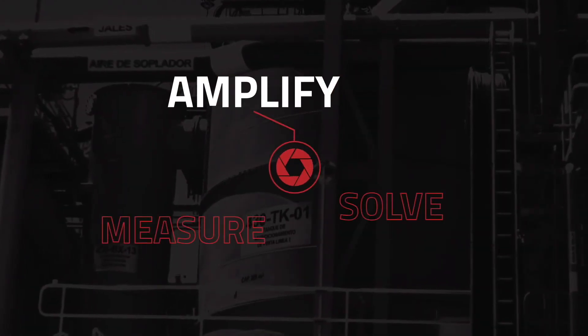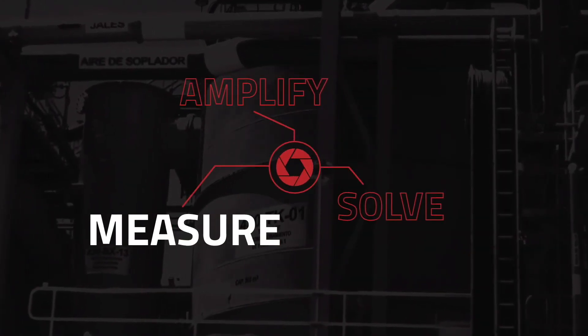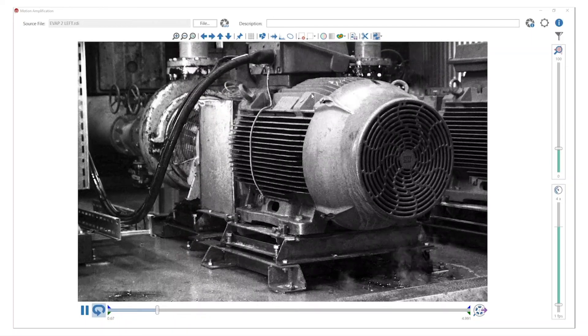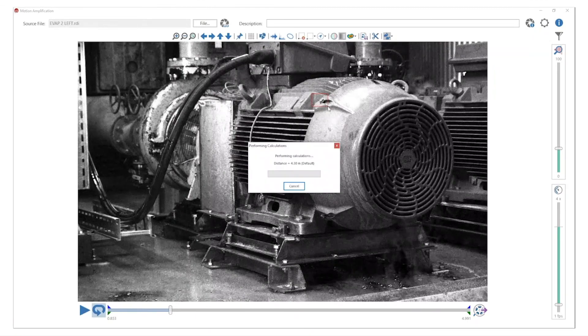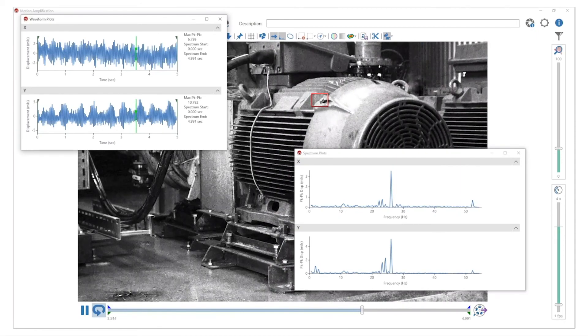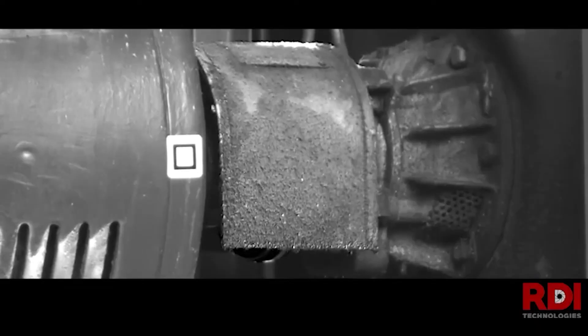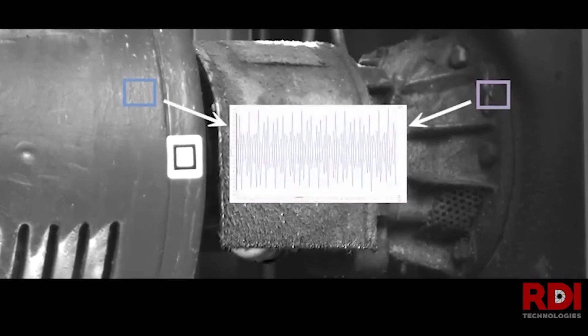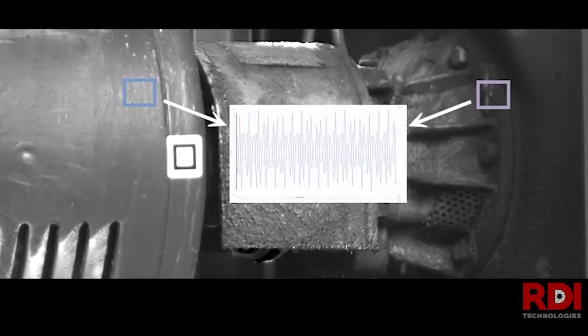Now that you have seen the power of motion amplification, I will walk you through how we measure and troubleshoot through the many features of the IRIS platform. The fundamental measurement taken with motion amplification software is displacement. RDI's products can measure and visualize motion down to less than 0.01 mils. The measurements are two-axis measurements showing X and Y from the viewpoint of the camera. The camera shows the overall motion and can show specific frequencies as well.